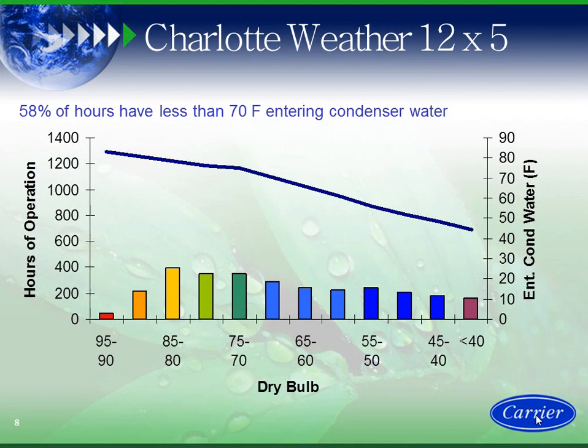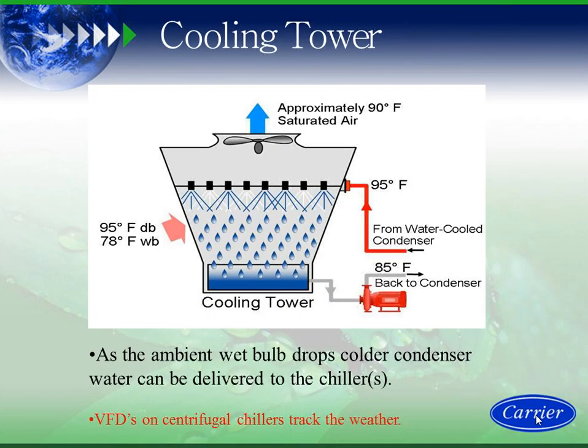So that's just some background on weather data and the determinants of energy efficiency itself. One of the main pieces of how we get efficiency is driven by this object called a cooling tower, which is something that we don't sell. But when we look at how we recognize efficiency on a chiller, actually any centrifugal with a variable speed drive, what that variable speed drive does is track the weather. So it tracks the wet bulb temperature in the tower, and that's how you get your efficiency benefits.